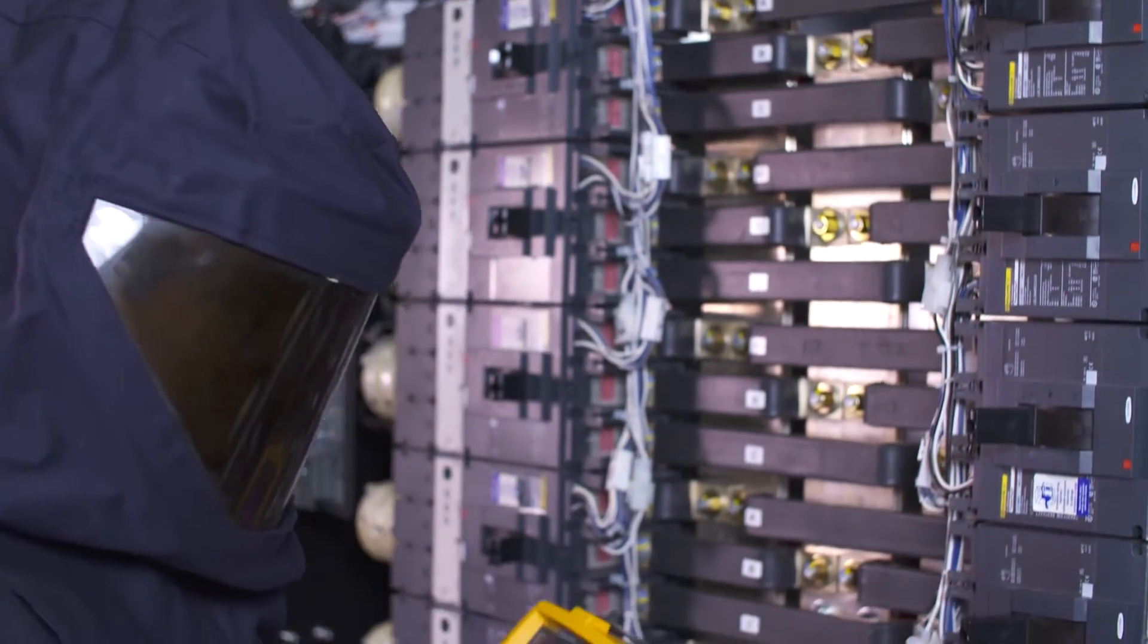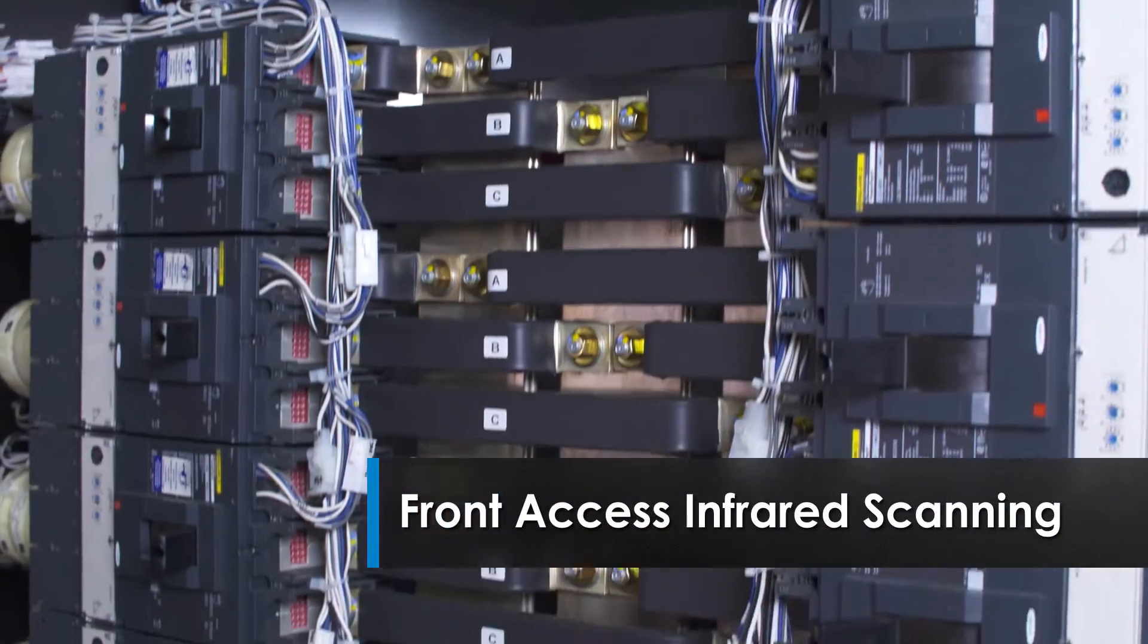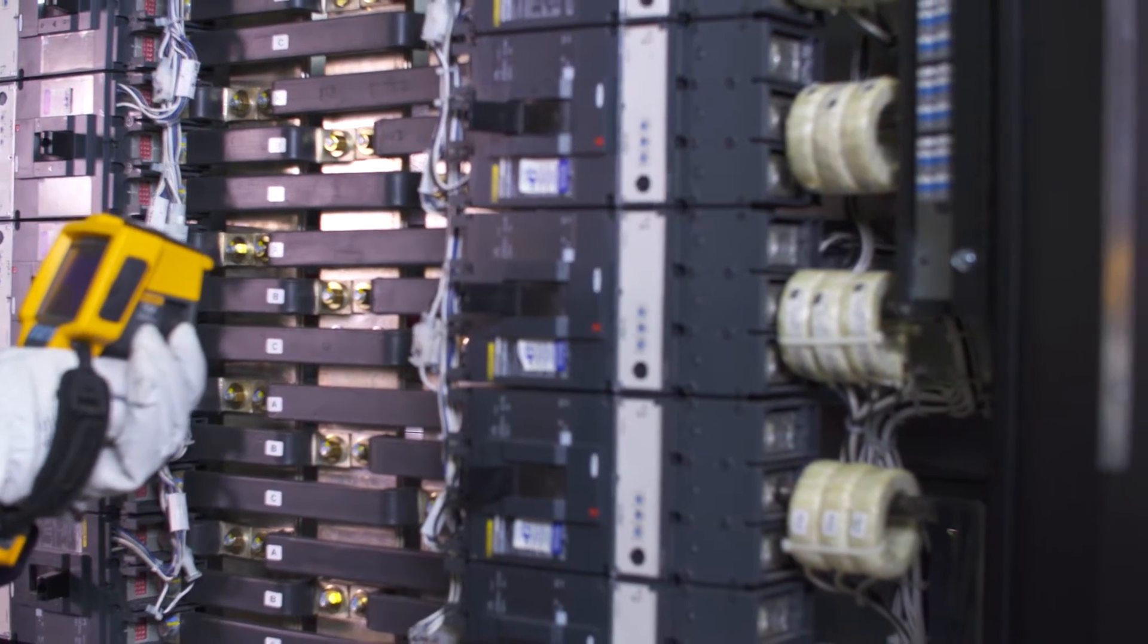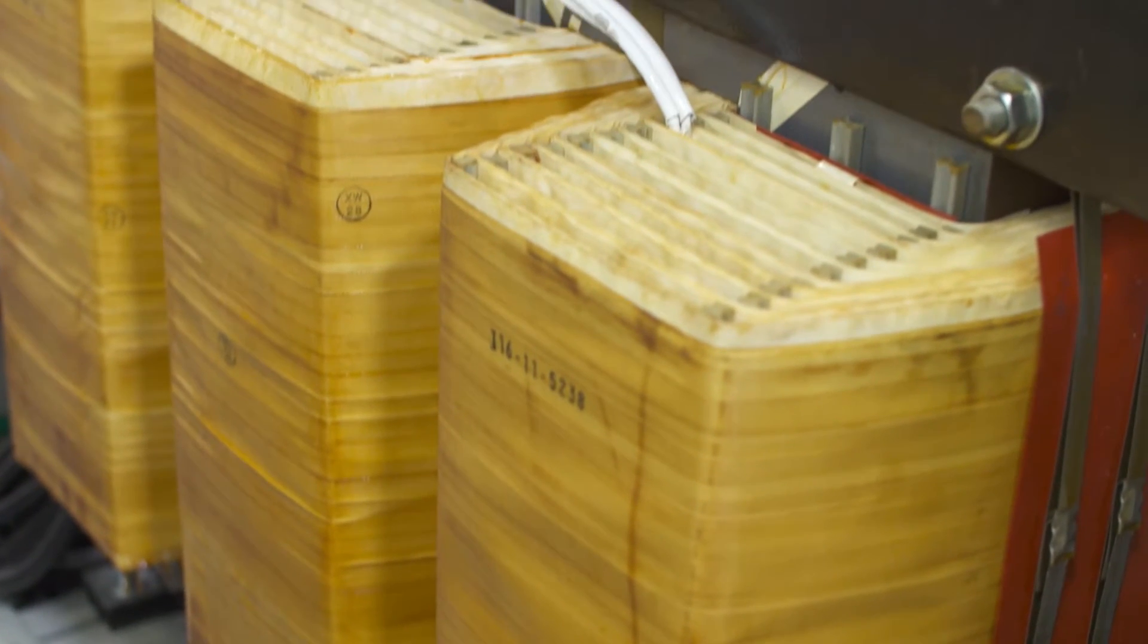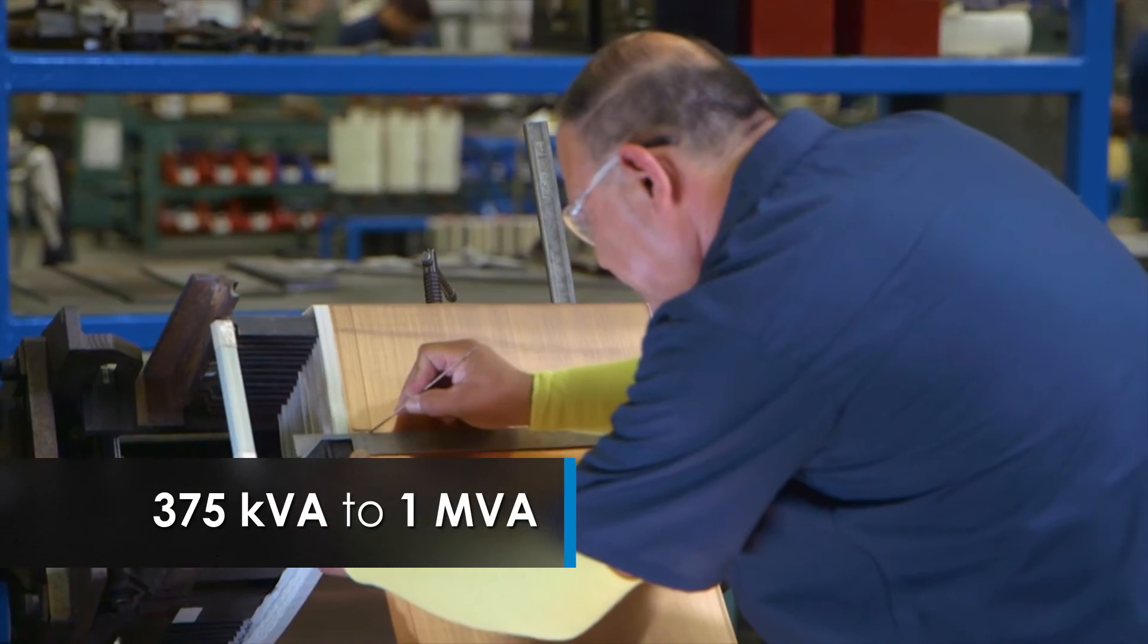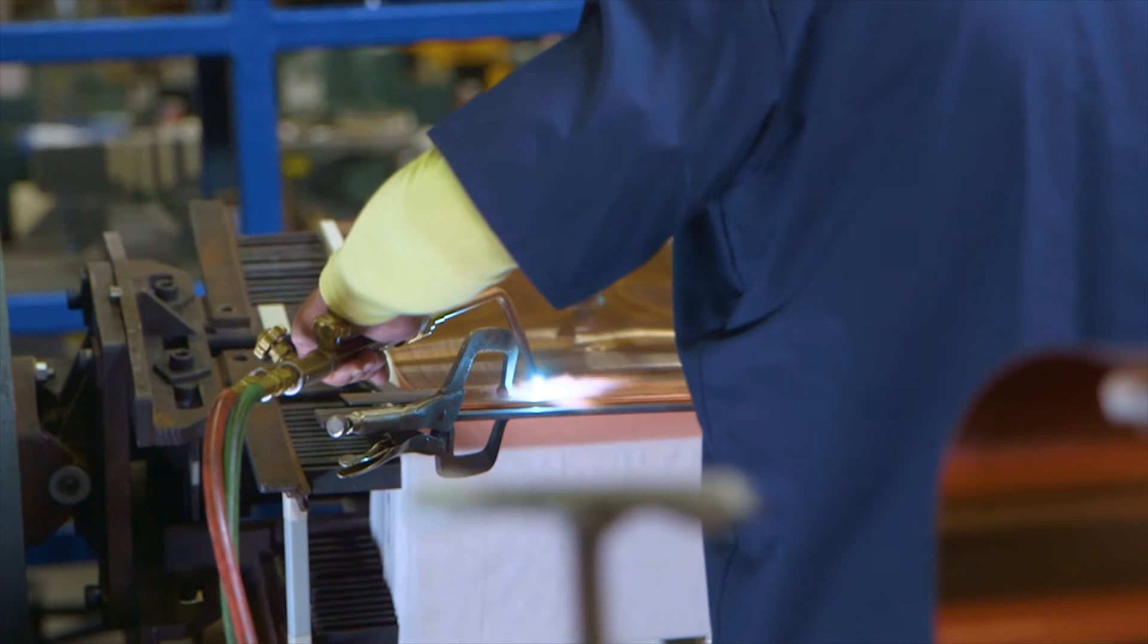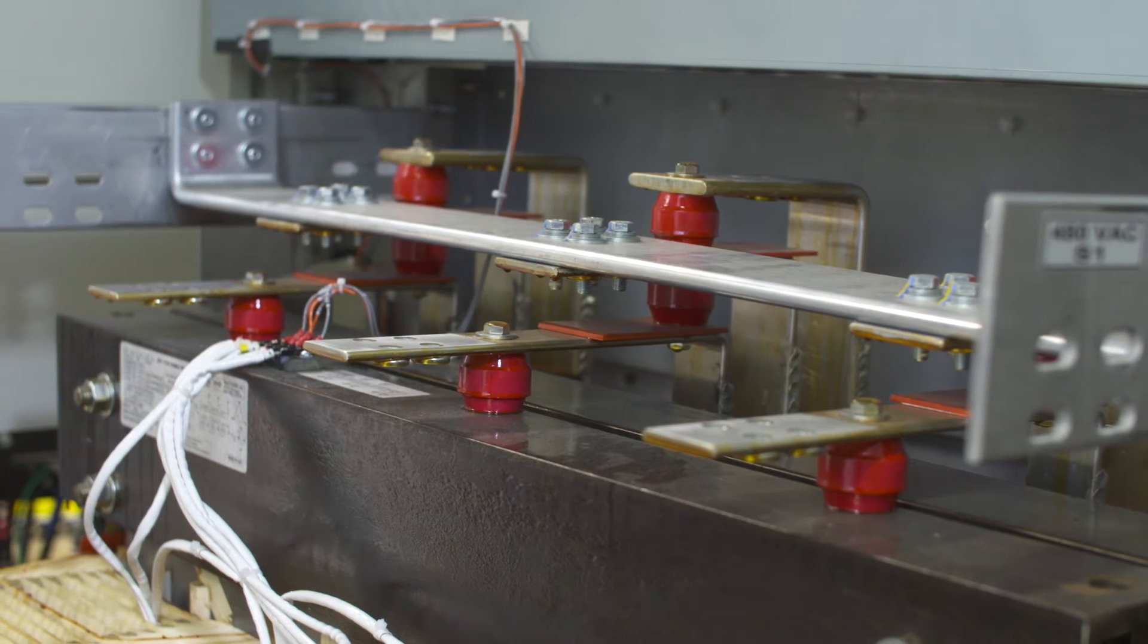The PowerHub 2 also features front access infrared scanning of the transformer, as well as all bolted sub-feed breaker connections. The DOE 2016 compliant transformer ranges in sizes from 375 kVA to 1 MVA. Optional multi-output transformer designs allow up to 3 different output voltages.